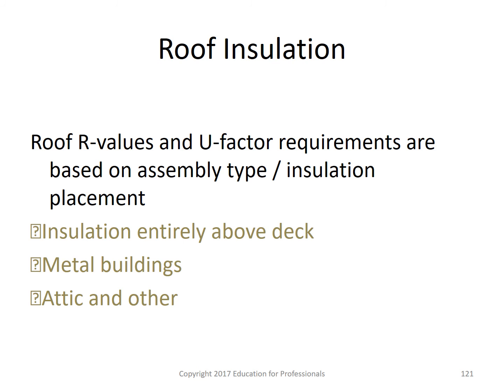Starting with roof insulation, we can take a look at how the roof insulation is calculated and estimated, and what categories it's broken down into. Here we see the roof R values and U factor requirements. In the eastern part of the United States, it's mostly the R value that is keyed on here. The three categories are whether the insulation is entirely above the deck, metal buildings, which create another category, and the third category, attic and other types of insulation installations.